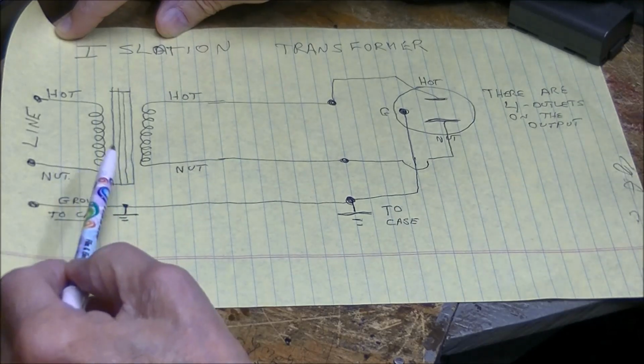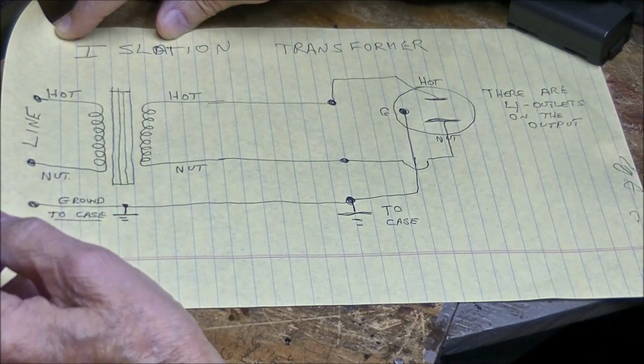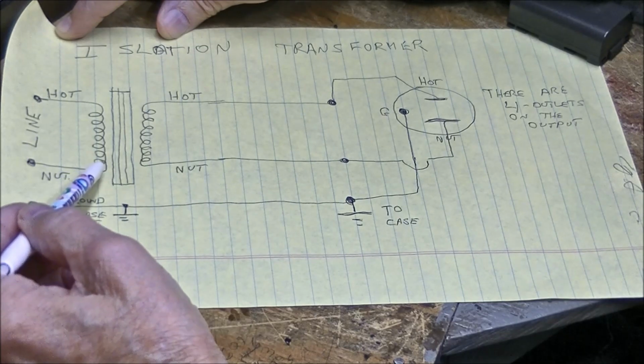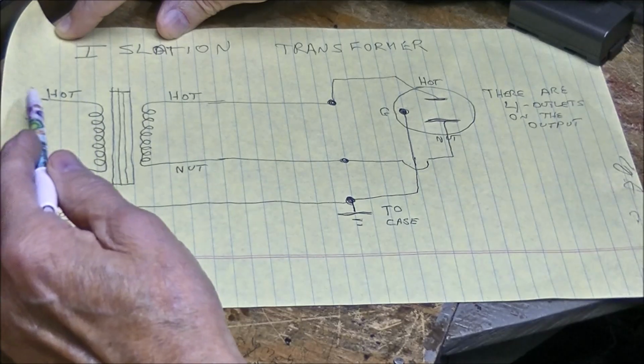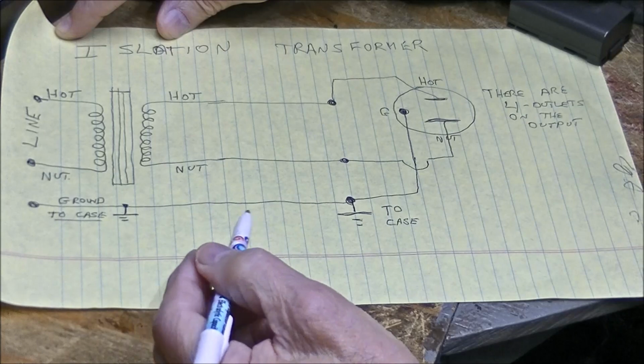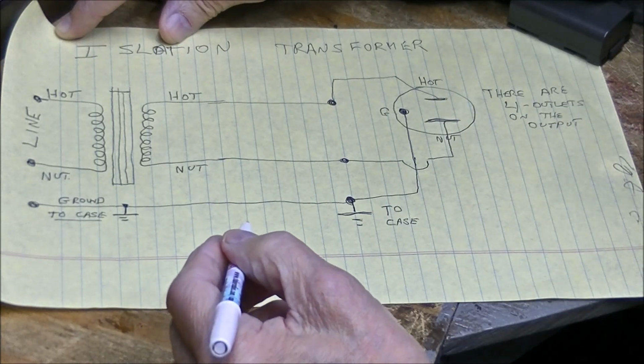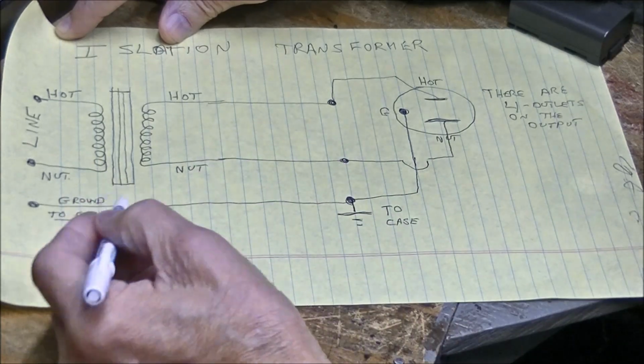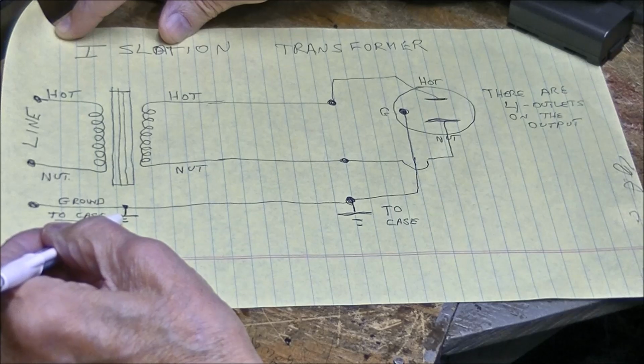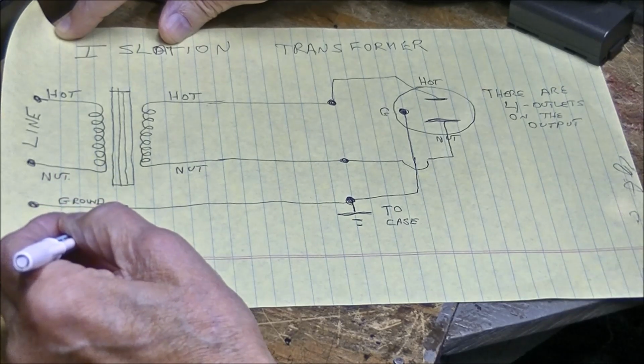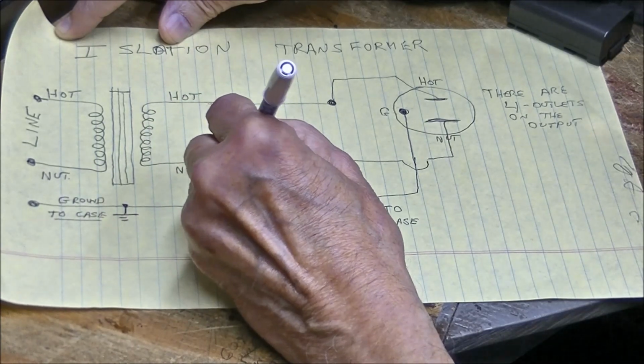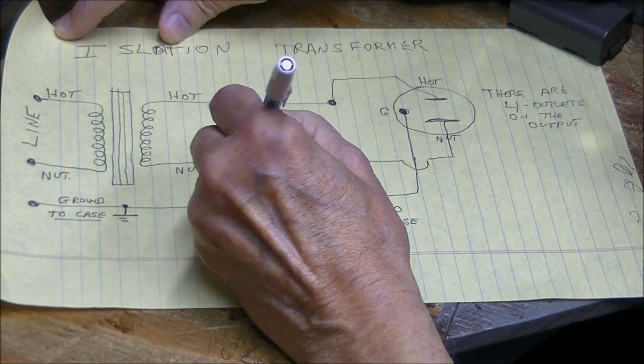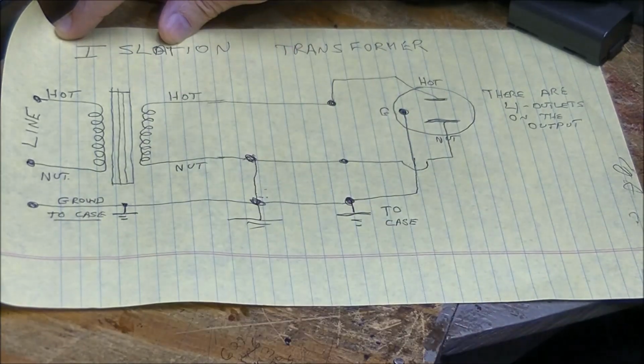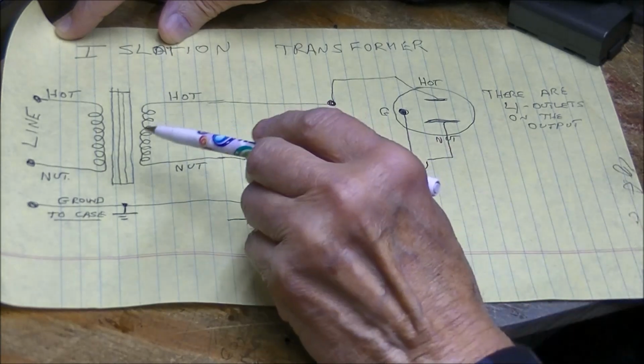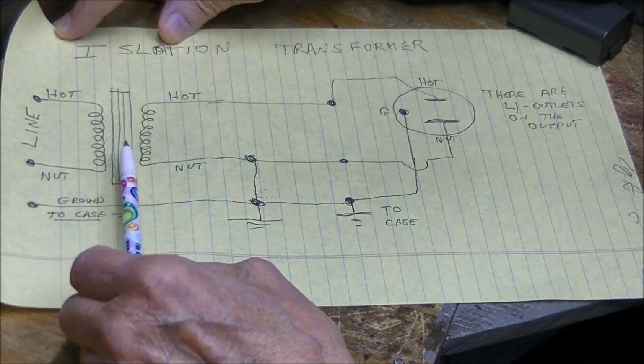On the neutral—your neutral comes in to the primary. When I got this, there was a common point where the ground, the green wire, and the white wire were grounded. In other words, this neutral was bonded like that, which made this thing a non-isolation transformer.